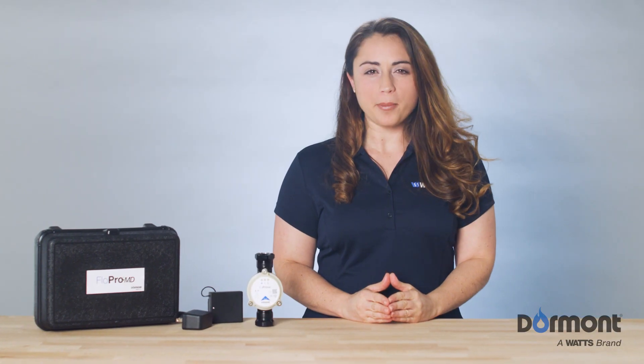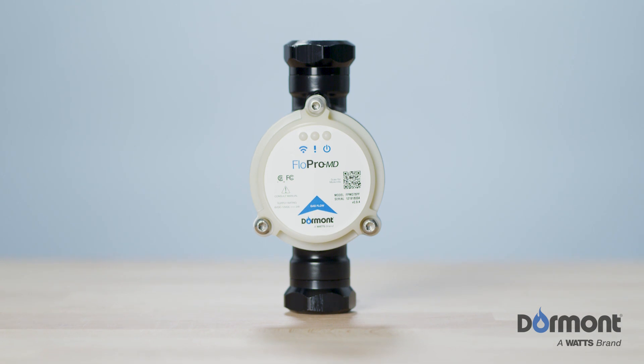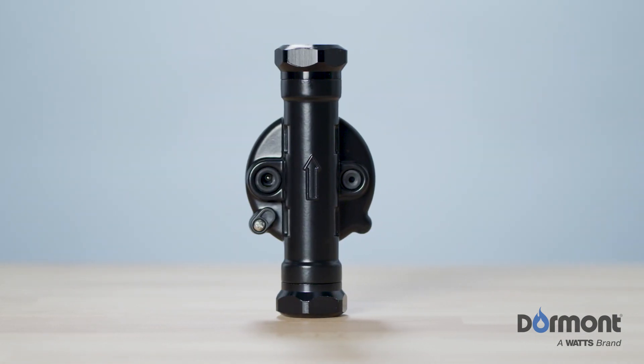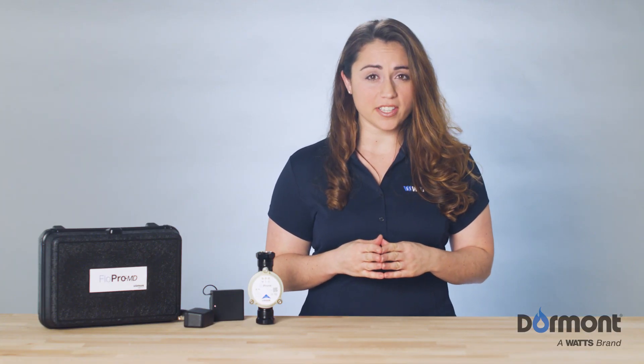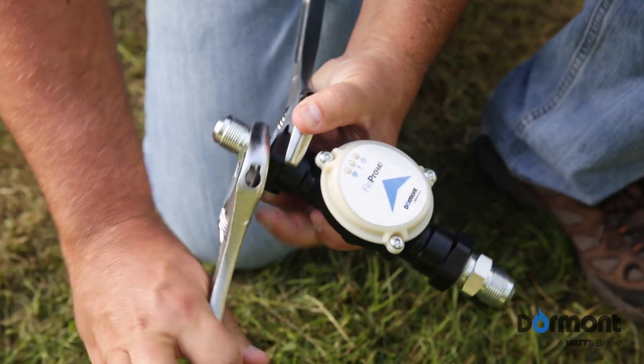To ensure proper installation, the FloPro MD label has a blue arrow signifying the proper direction of gas flow through the device. There is also an arrow permanently embossed on the device aluminum housing for the same purpose. Using two adjustable wrenches, or a pipe wrench if there is no hex surface, complete the final gas tight connection between the mating NPT threads. One of the adjustable wrenches must be placed on the hex surface of the FloPro MD device while making the final gas tight connection.